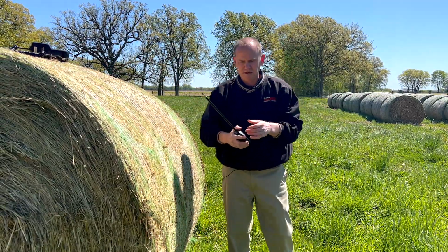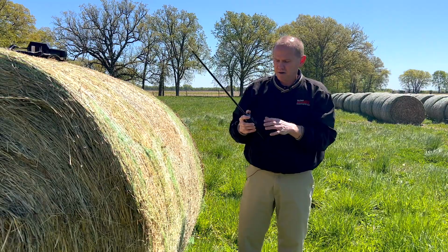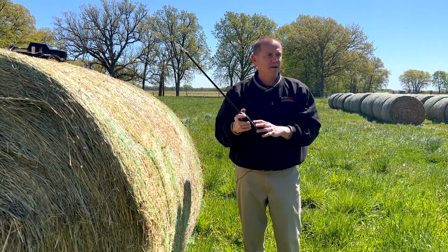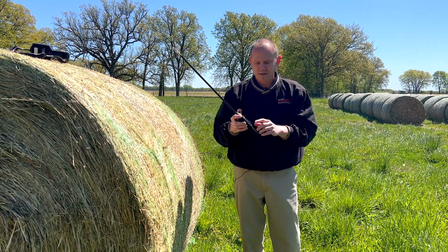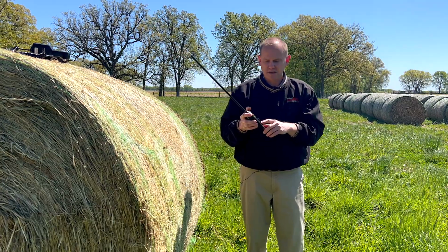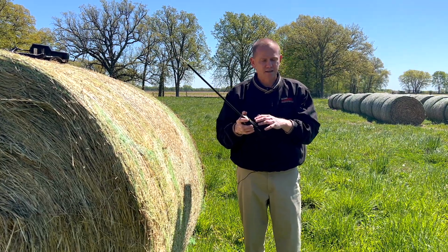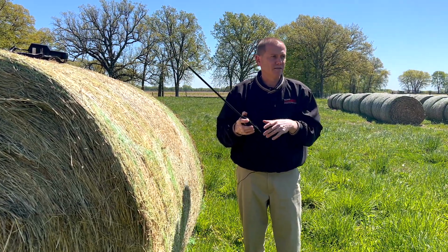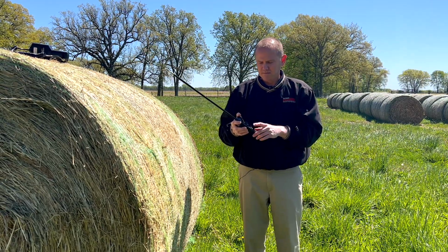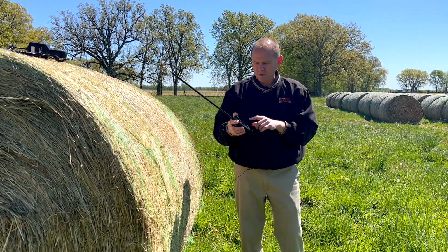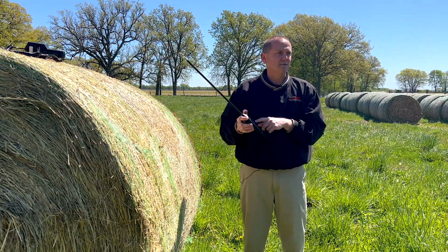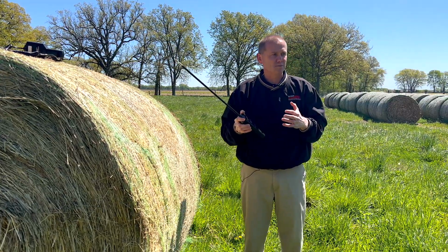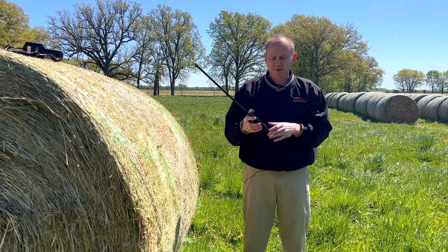HT Pro, as you can see here, the probe is fixed to the readout. It does have 4 different buttons on it. One's for the backlight. You can just hit it if you want to have a backlit area on it to read that number a little bit better. If you don't need it, you can switch it off. Then you have your moisture and your temperature as well. And then the check button on the right-hand side is actually just for calibration purposes. You don't need to touch it any other time.